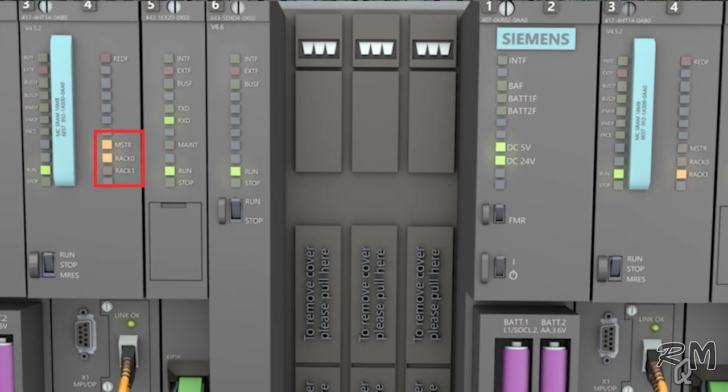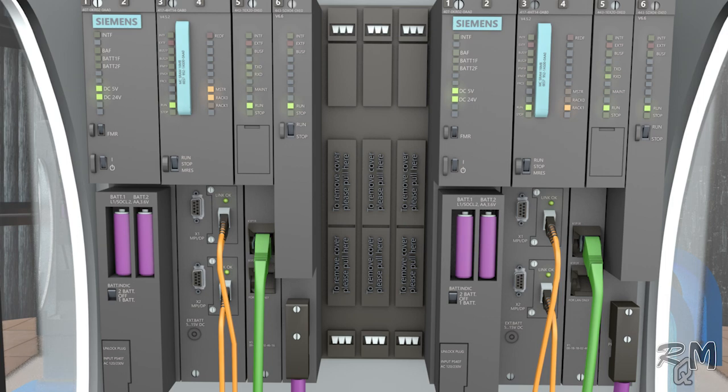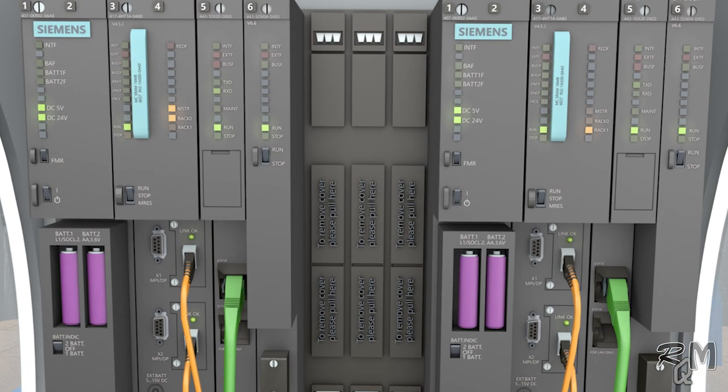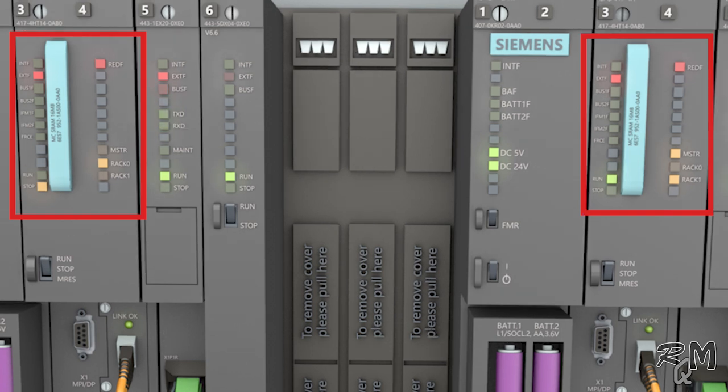Master LED of rack 0 is on which indicates active CPU. Rack 1 master LED is off so it is hot standby. Do not be confused with the word master. They are not installed in master slave configuration. They are redundant CPUs with same program and with equal authority. It means if due to some fault rack 0 CPU goes offline, then rack 1 CPU immediately takes control of the system.